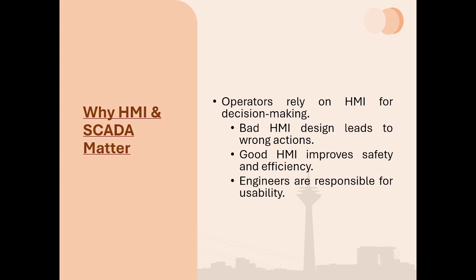An HMI means human-machine interface, and is simply the window through which an operator sees and controls the process. A SCADA system, which stands for supervisory control and data acquisition, sits above the control system and provides plant-wide monitoring. It monitors the alarms, the trends, and also the historical records. So if anything happens, you can trace through the SCADA. These systems do not control the process directly. They only support human decision making. So if the information presented is unclear, even a well-designed PLC system can be operated wrongly.